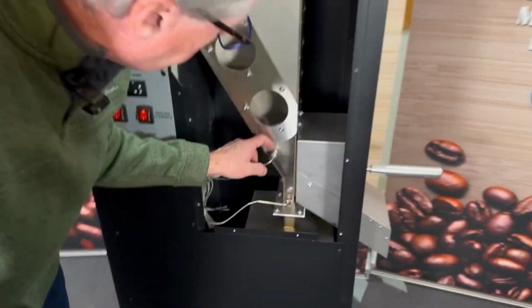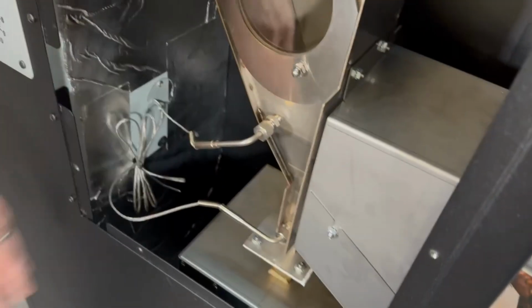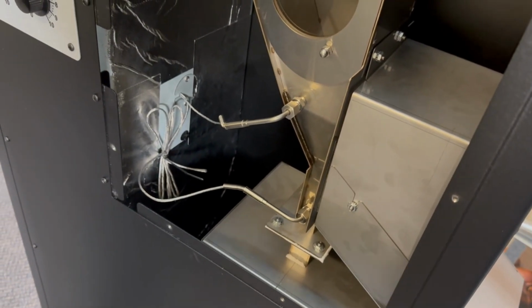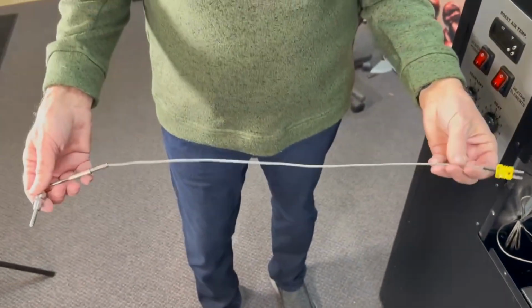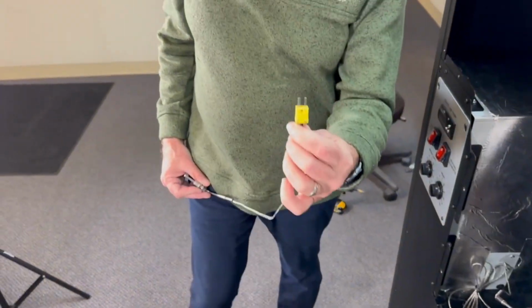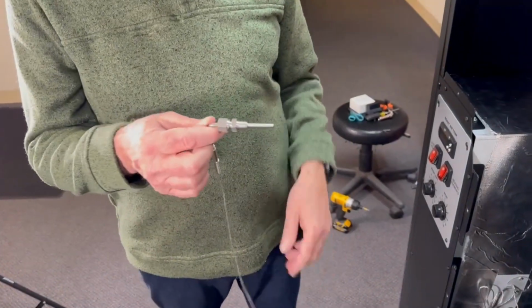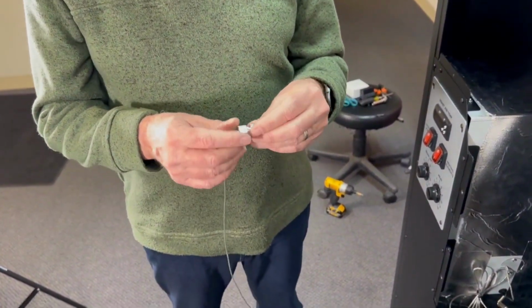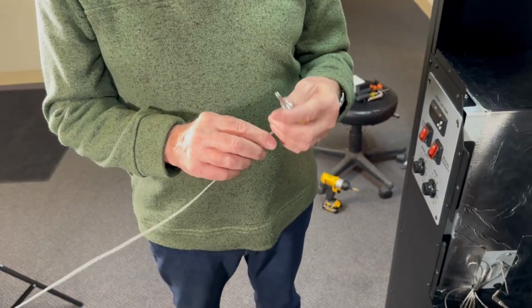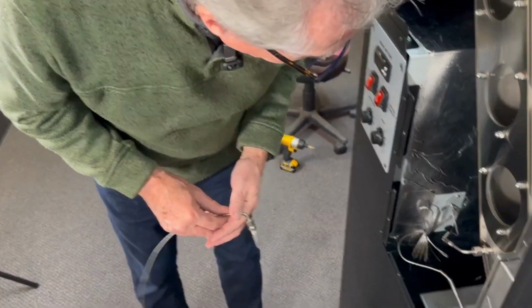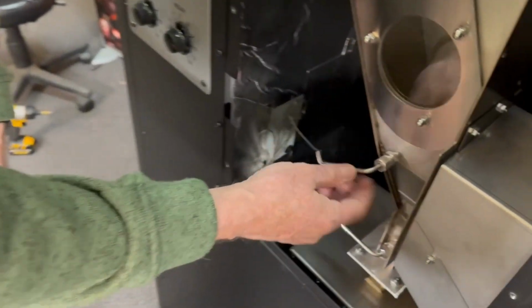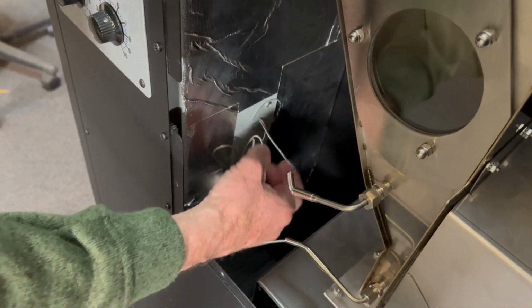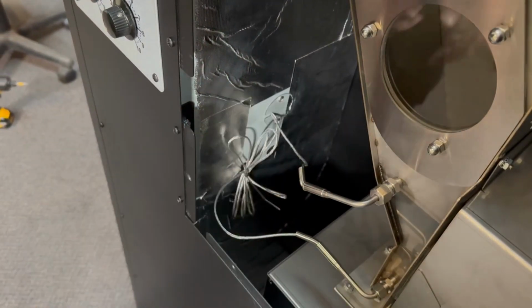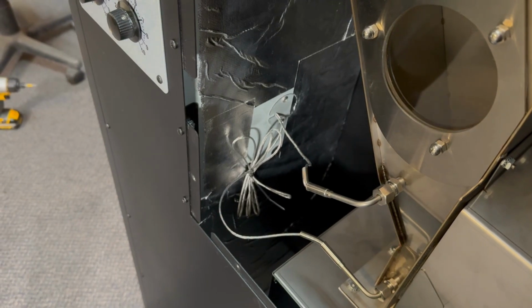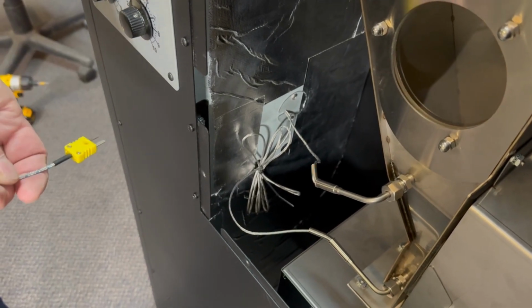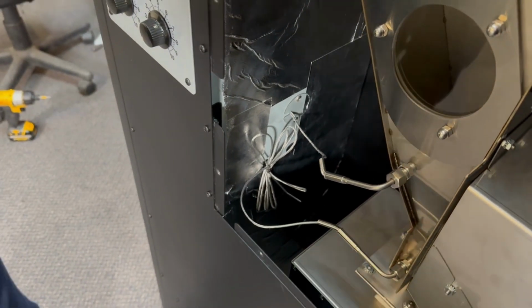This is the bean thermocouple, and that would be this wire here. On one end, it's going to have the yellow connector. On the other end, it's the standard NPT 1/8 inch. And to change this out, we're going to take this out right here. We take that out, and that covers up a gap large enough to pass this through. So I'm just going to pull one of those out so you can see.